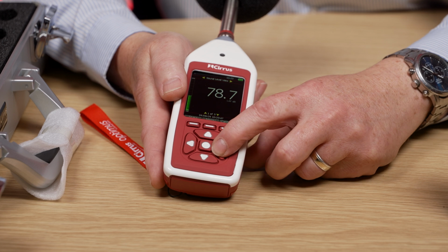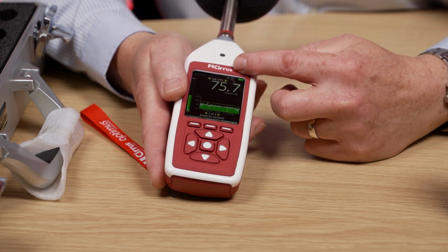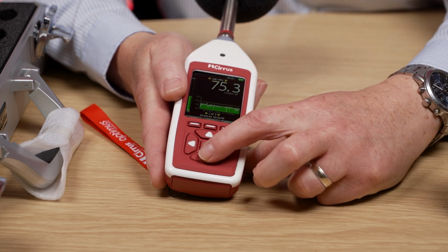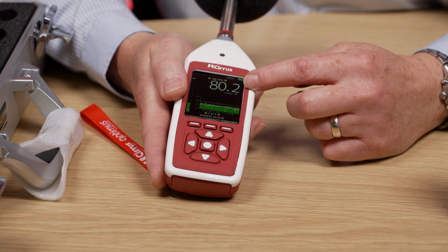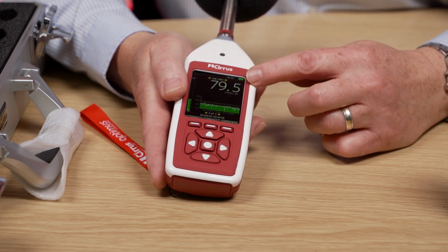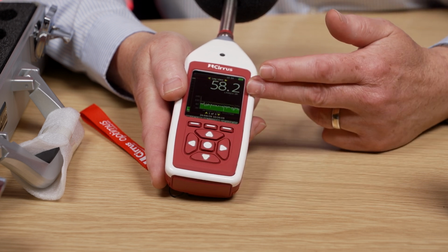As you go through each of these screens, in this case for the LEQ view, remember this is the logarithmic average, I've got 3 pages. If I go down, page 2 gives me the C-weighted instantaneous or 1 second average. If I go down again, Z-weighted. I'll go down again, I'm back up to page 1.